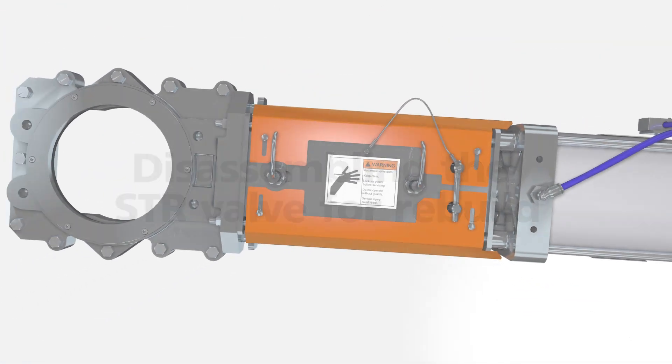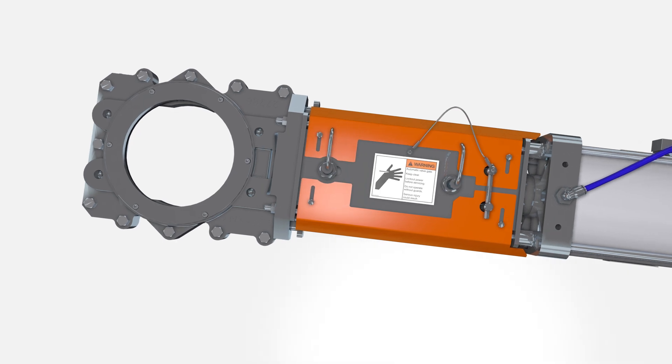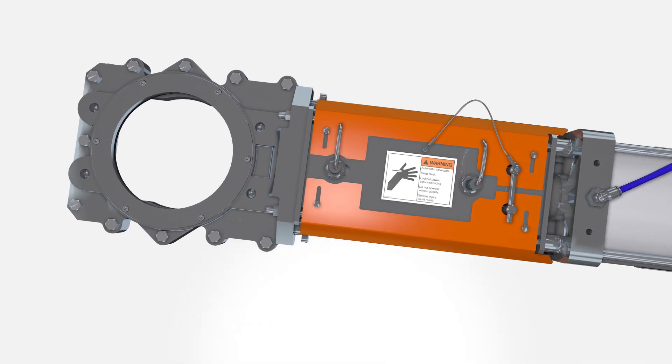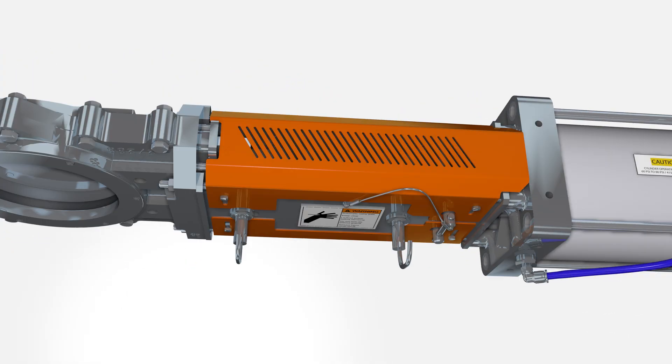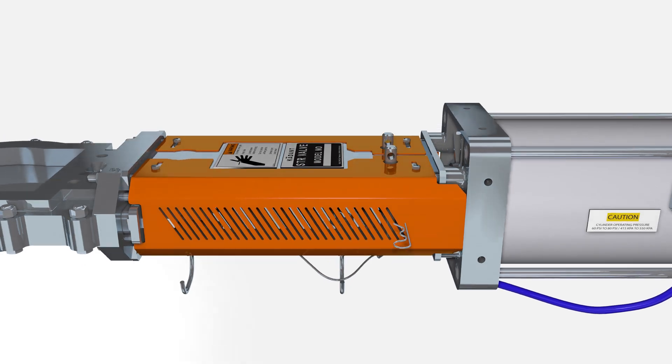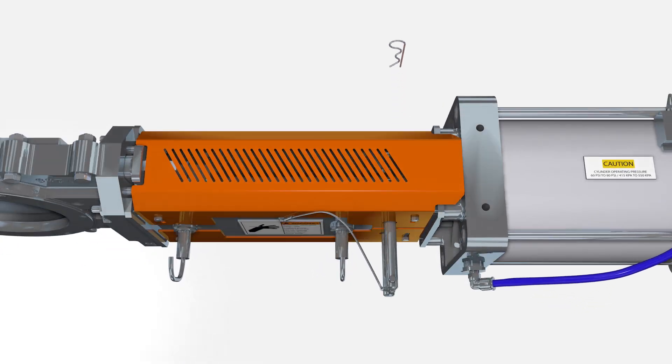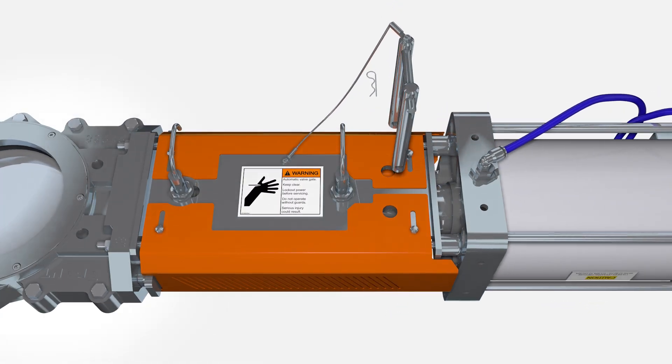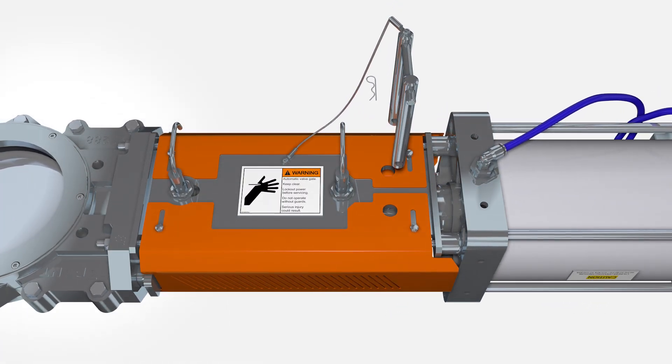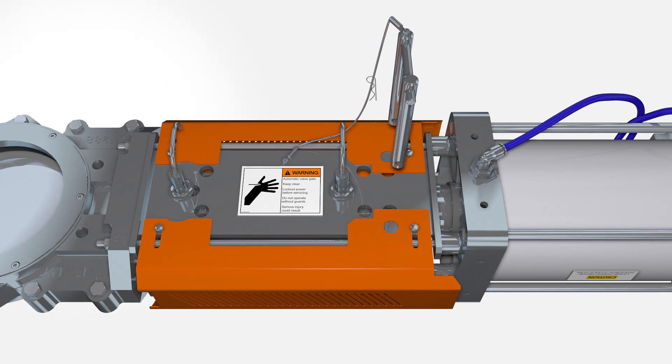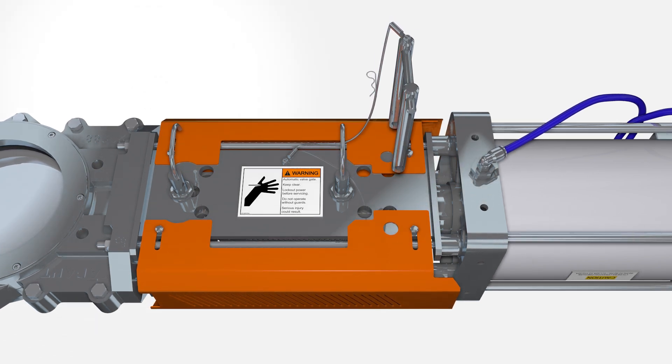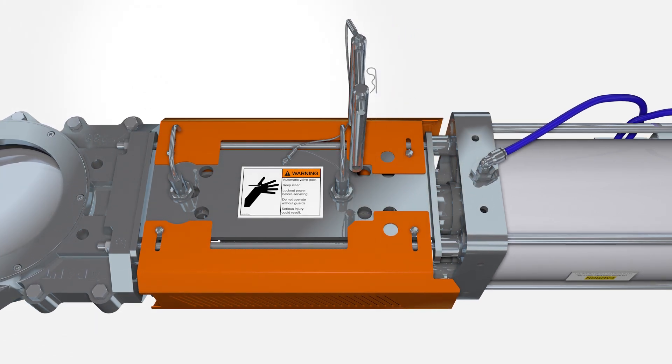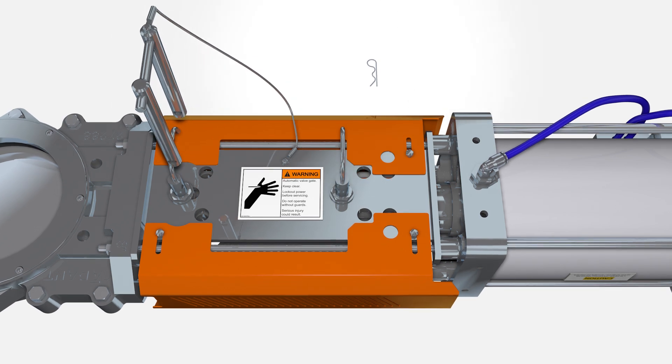Disassembling the STR valve for rebuild. Begin the disassembly by closing the STR valve. Now remove the locking pin from the storage position. Loosen the guards and pull them apart to reveal the open and closed locking position hole. Secure the locking pin in the closed position.